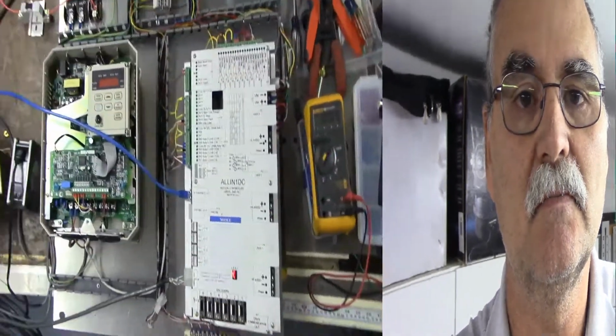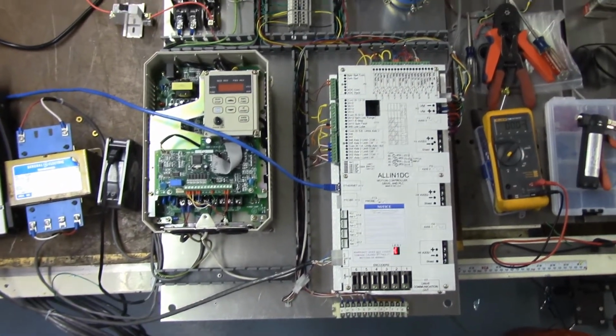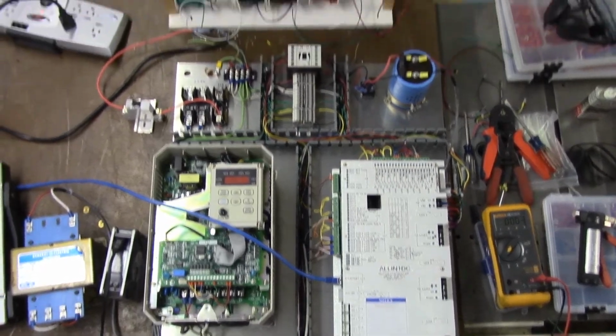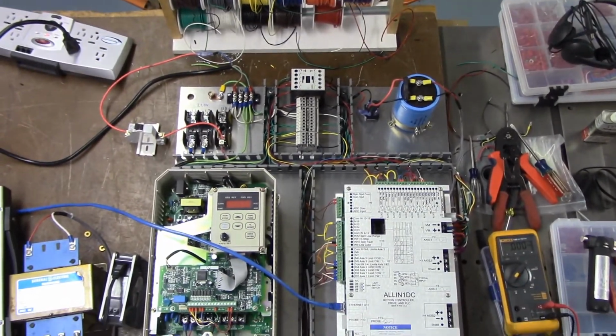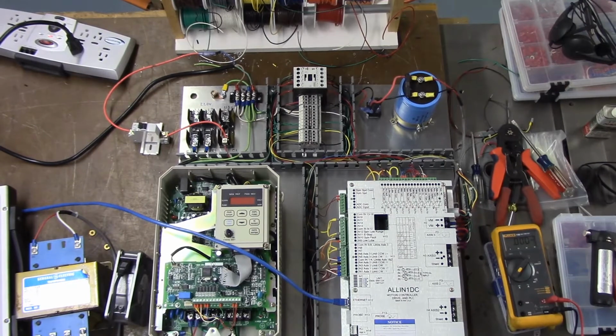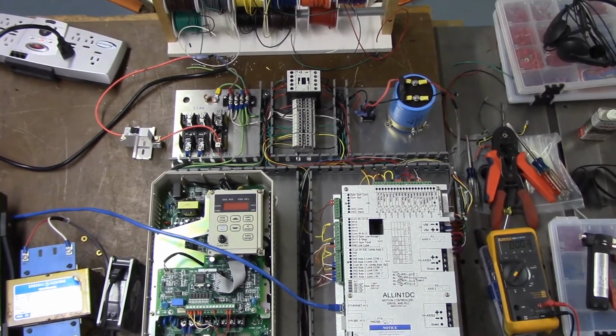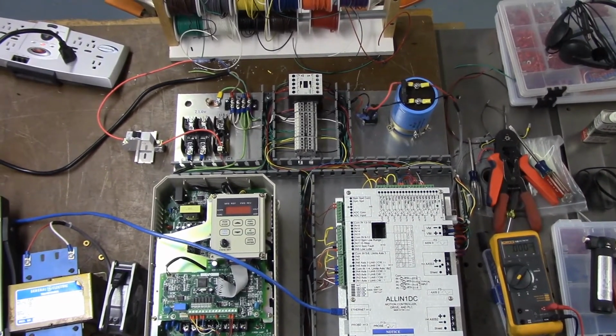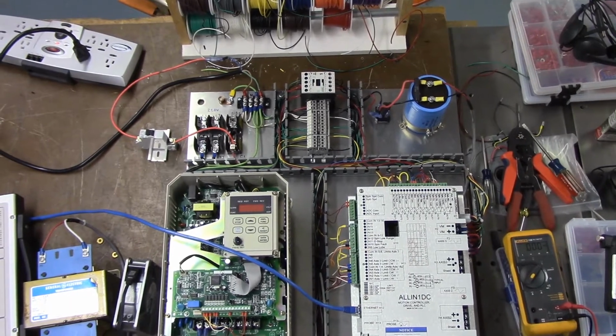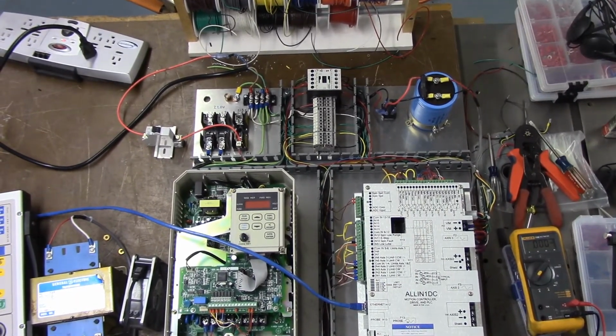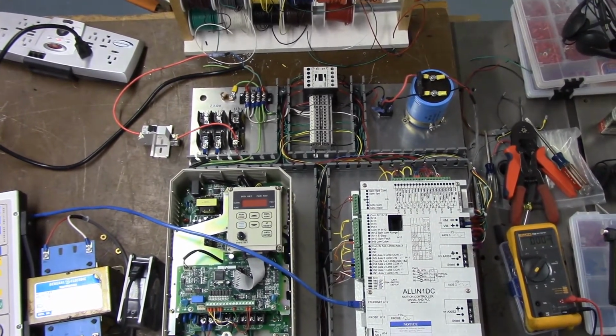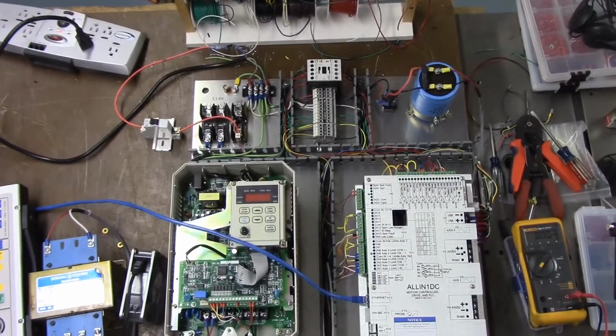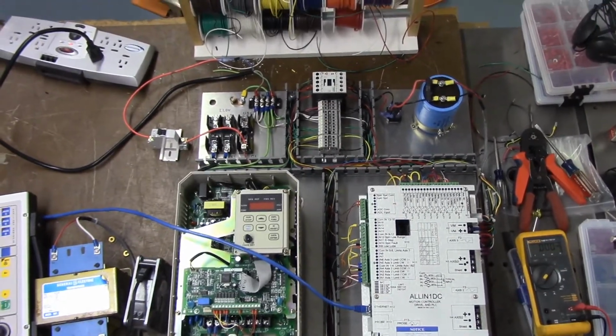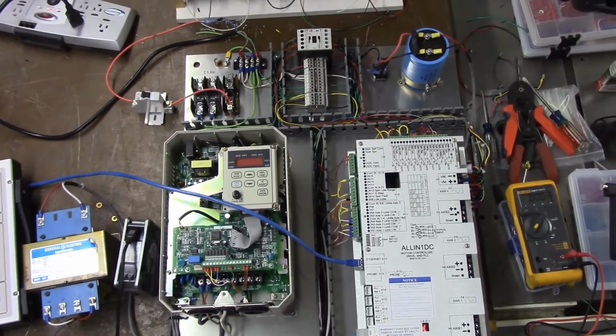Let me turn you around and let you take a look. Okay, there you can see the all-in-one DC and the back panel. You see the bridge and the DC capacitor in the upper right corner. Right in the middle top, you'll see the e-stop relay and the typical 15 position terminal block. I use DIN style terminal blocks. And then lower left there you see the VFD.